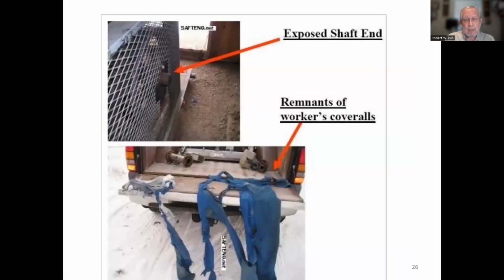Yeah. This is an exposed shaft end. And in this particular incident, the remnants of the worker's coveralls, the coveralls got caught and he didn't get hurt, it just ripped them up. But that's what happens with an exposed shaft end.